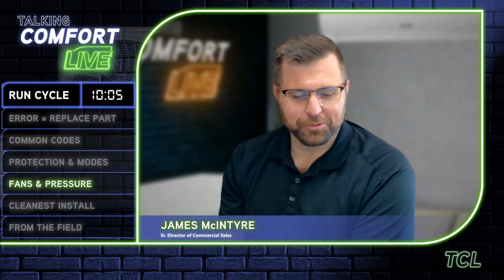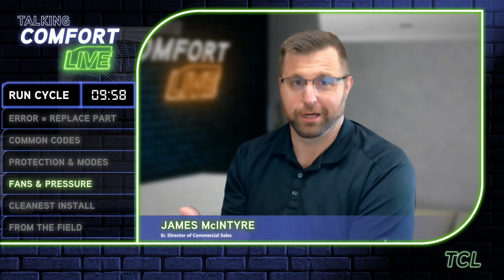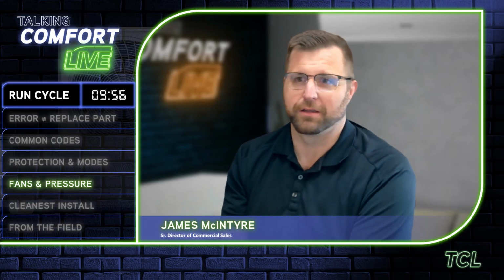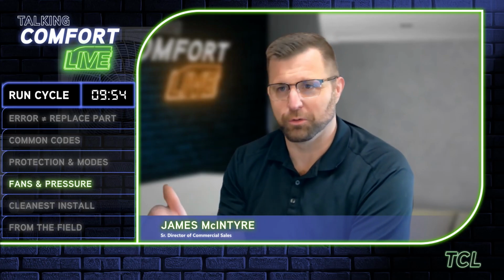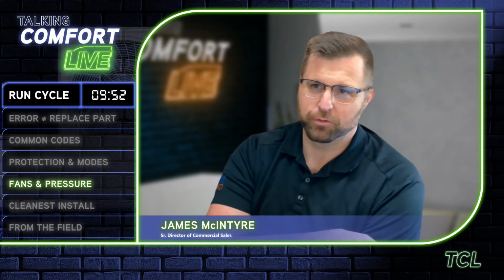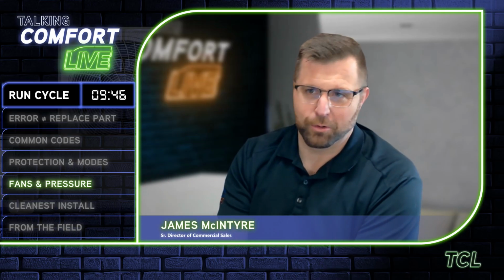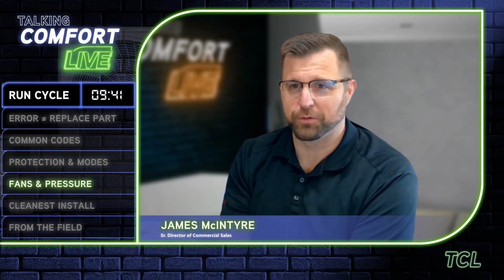No. So the compressor itself keeps itself cool using refrigerant. Okay, why is that refrigerant hot? Why is that not enough refrigerant? What's reducing the volume of refrigerant going into our compressor? If we have a reduced volume of refrigerant across the entire system, that's like saying it's low on refrigerant. So normally you're thinking, okay, if it's low on refrigerant, why is the compressor getting hot?